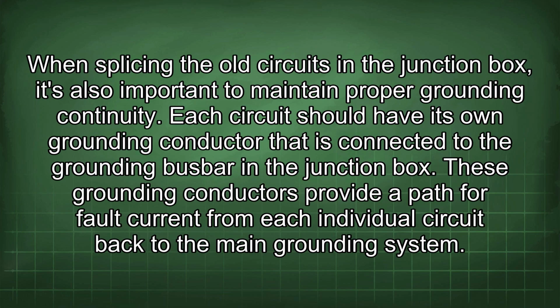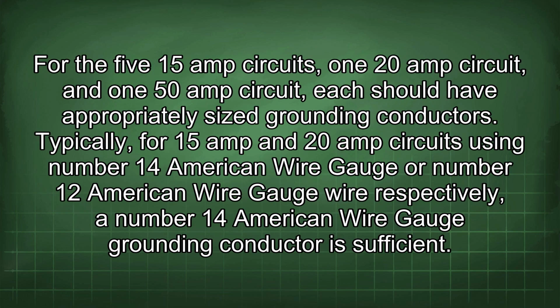When splicing the old circuits in the junction box, it's also important to maintain proper grounding continuity. Each circuit should have its own grounding conductor that is connected to the grounding busbar in the junction box. These grounding conductors provide a path for fault current from each individual circuit back to the main grounding system. For the 5 15 amp circuits, one 20 amp circuit, and one 50 amp circuit, each should have appropriately sized grounding conductors. Typically, for 15 amp and 20 amp circuits using number 14 American wire gauge or number 12 American wire gauge wire respectively, a number 14 American wire gauge grounding conductor is sufficient.